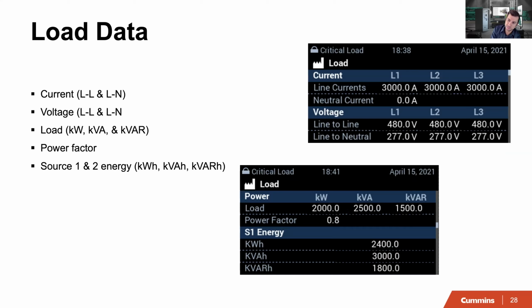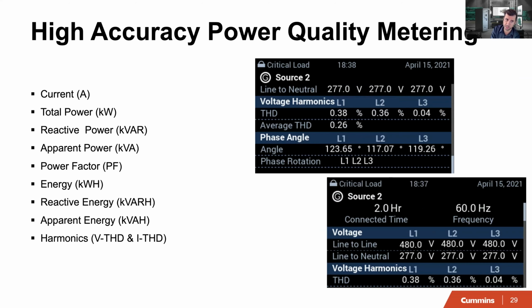There is load data to keep you in touch with your system, right? The total current, neutral current if there is any, line-to-line voltage, line-to-neutral voltage, and also energy, kW, kilowatt-hours, and reactive power as well. There is high accuracy power quality metering built into the control, so we don't need to have a separate component for that, where we get current, voltage, power factor, real and reactive energy and harmonics. You might want to check, maybe there's a problem in the load. Maybe we have switching power supplies with IGBTs that are firing, and it's causing some harmonics in the system. All the loads that are connected to the transfer switch, we can see that data live on the control itself.